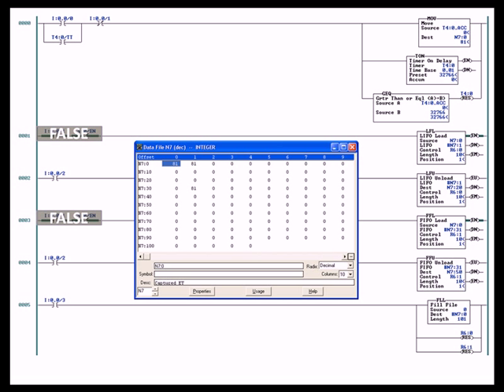The last rung using the fill file, when you toggle switch 3 or the switch wired up to the I/O terminal that controls the state of memory location I:0/3, when that goes from the false to true transition, it will fill N7:0 for a length of 101 with zeros.